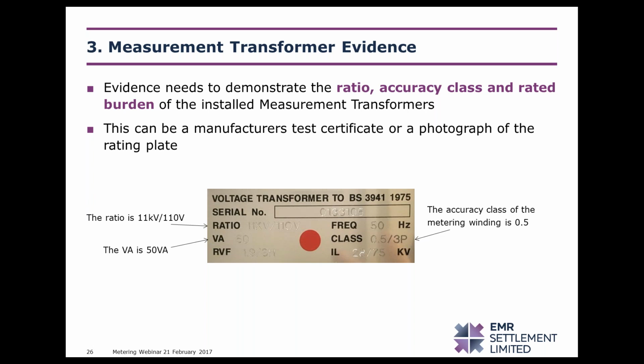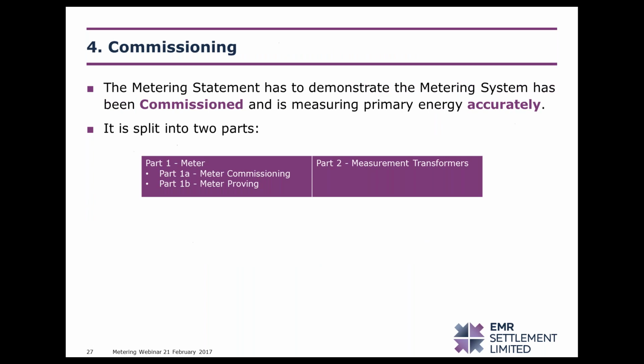Looking at the example of a voltage transformer rating plate here, the information we are looking for is the ratio, which is clearly visible as 11 kV to 110 volts. The rated burden is the VA, which in this example is 50 VA, and the accuracy class of the metering winding is 0.5. You can also see the serial number of the measurement transformer. We would need something to this standard to be submitted as part of the metering statement for it to be compliant with the rules.